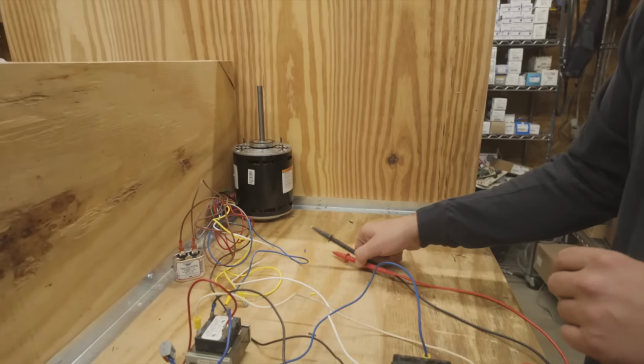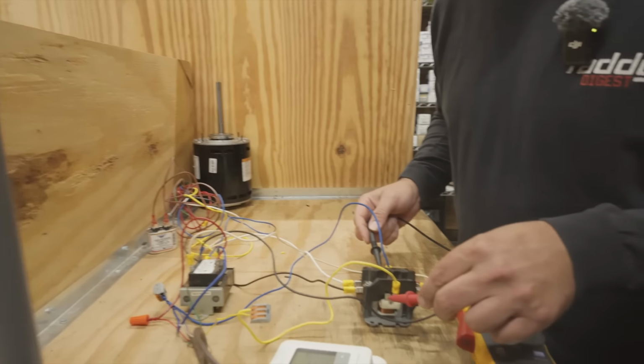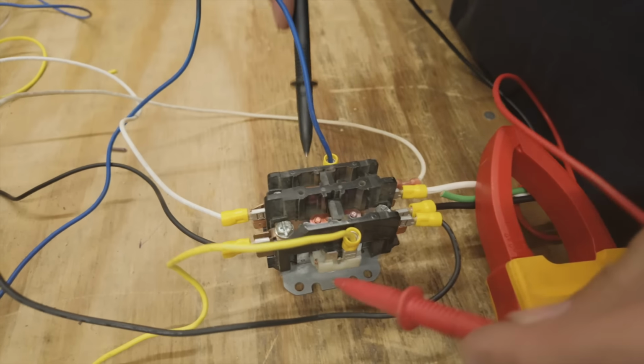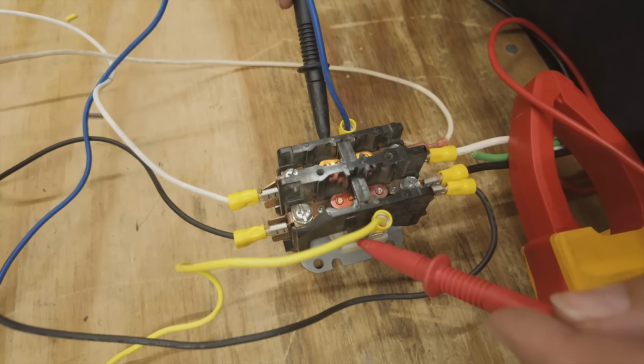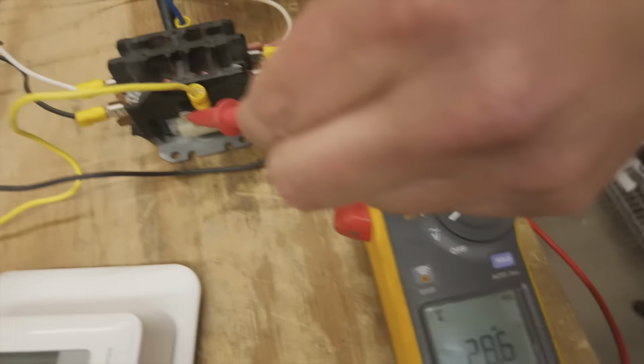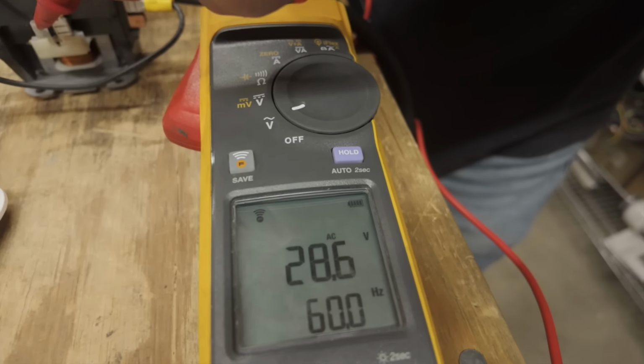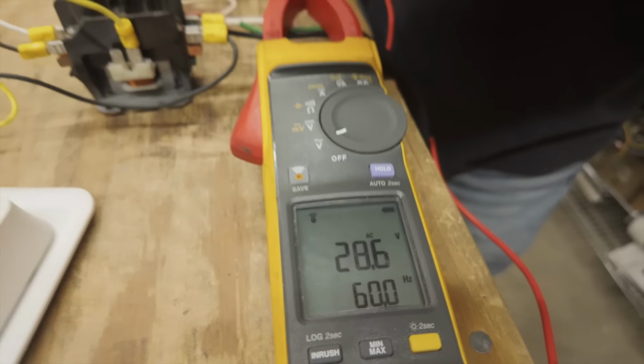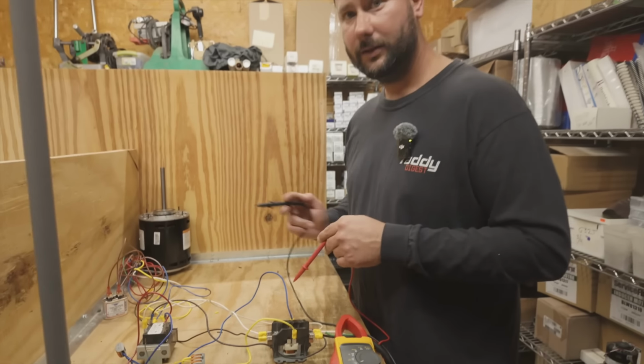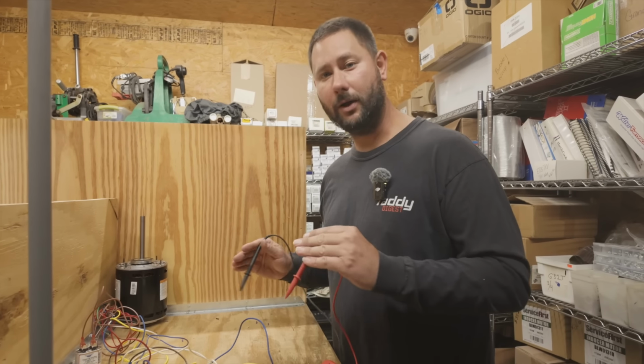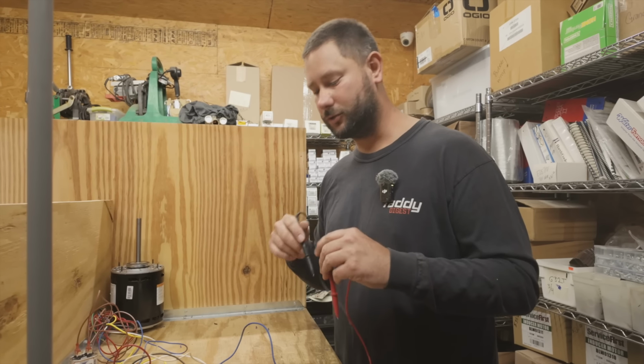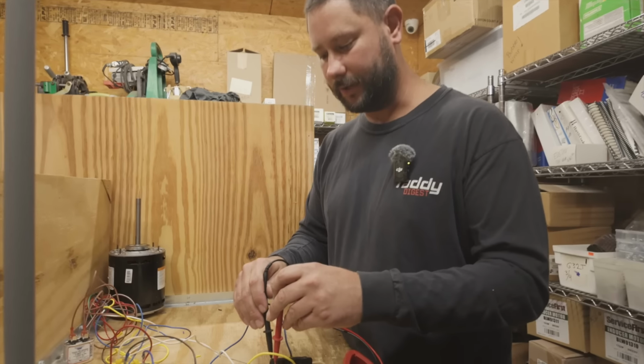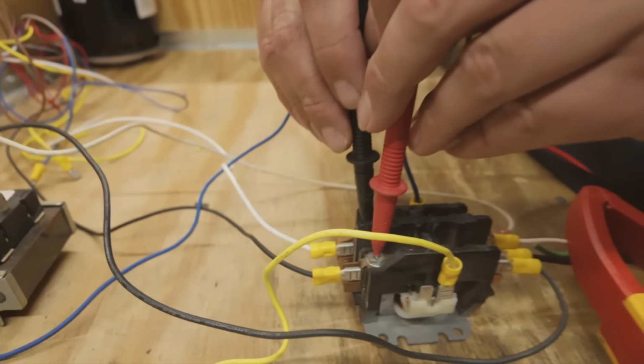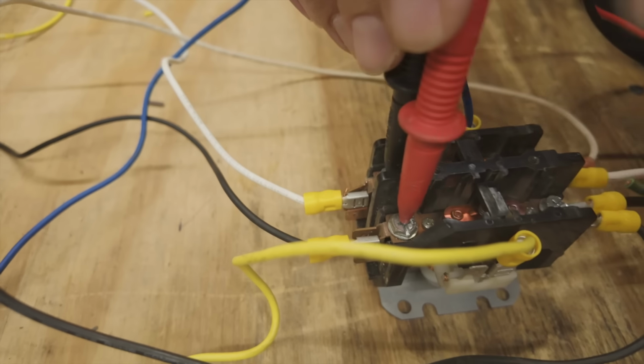Now, let's check at the coil and see what we got. Blue to yellow. Here's our coil. What do we got? 28 volts. That means we got power to our motor. Now, if you don't know anything about wiring motors, I've got a video, and I'll put the link in the description so you can learn more. But on the load side of the contactor, we should have 120 volts.